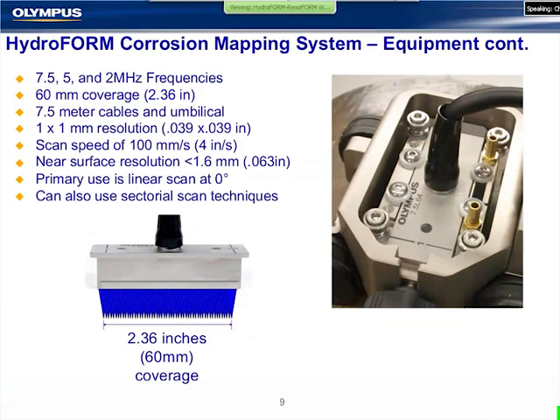The HydroFORM system also uses the large 1 millimeter pitch version of the probe. So using the standard default aperture of 4 elements, that gives us approximately a 60 millimeter coverage, or what we would call a stroke. So the scanner's moving in one axis, and the stroke is the electronic axis of the probe. Now probes are also available for this configuration at 5 and 2 megahertz. The umbilical is customizable, but comes in a standard 7.5 meters.